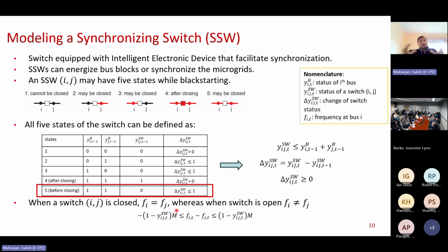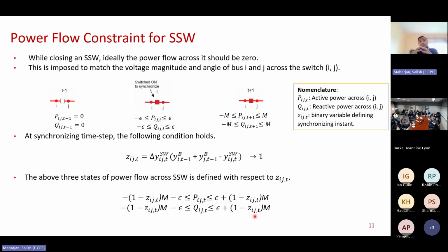So it can also have the same 5 states as an energizing switch, but the difference is in the 5th state. In the 5th state, when both the buses are active, the synchronizing switch can be closed. So we can model all these states by only 3 equations, and the frequency transfer condition can also be modeled. But it is not sufficient to model the synchronizing switch with only that equation. We also need to ensure that while closing a synchronizing switch, the voltage across the buses and the angle across the buses are sufficiently close, right?